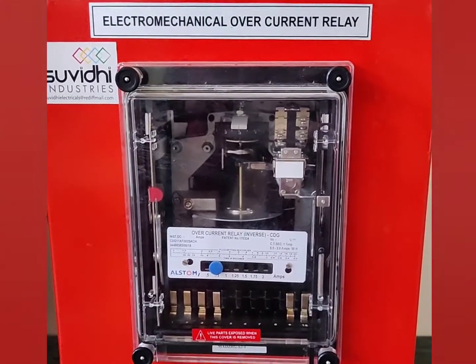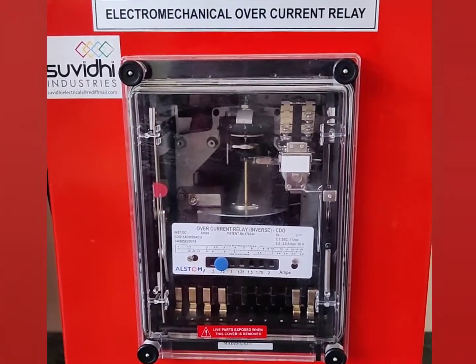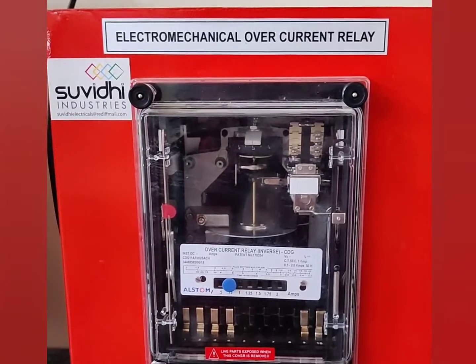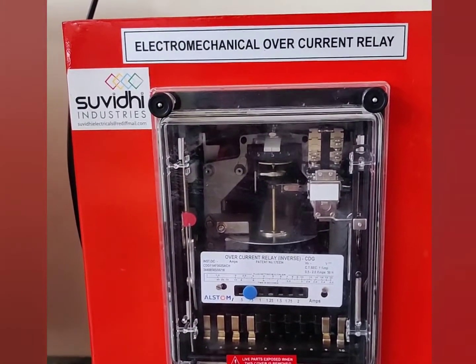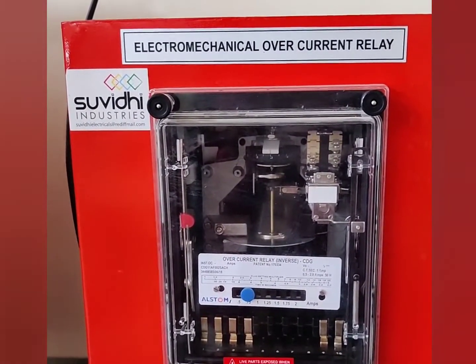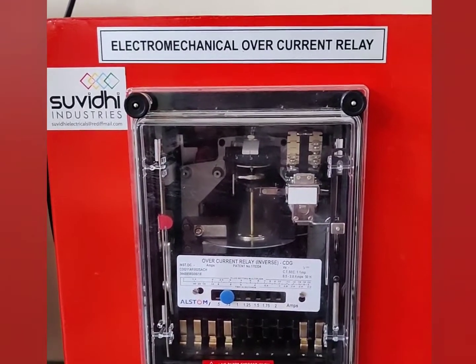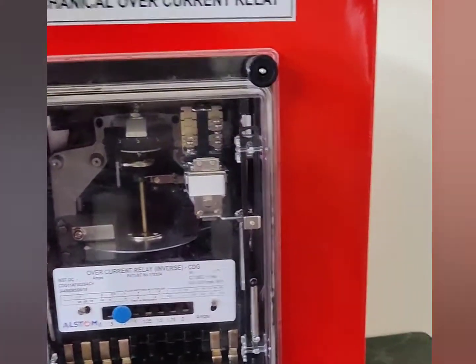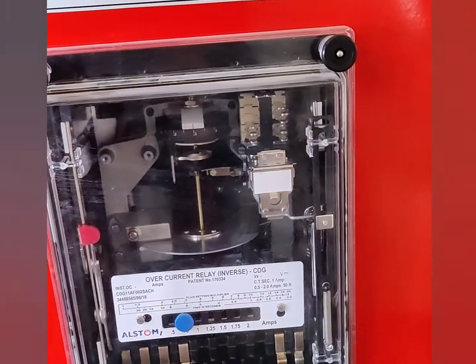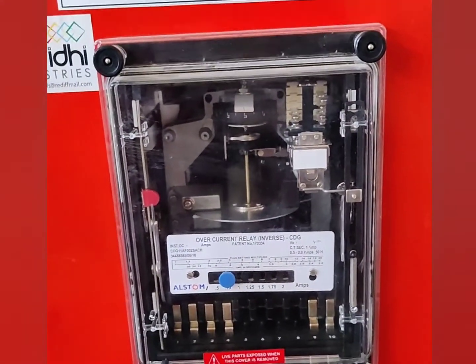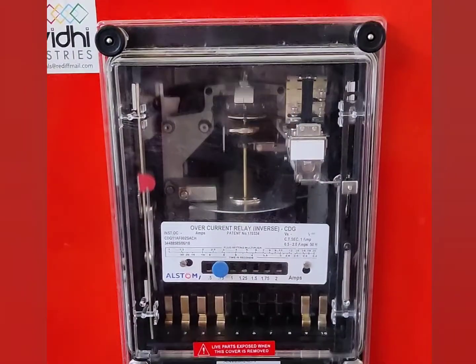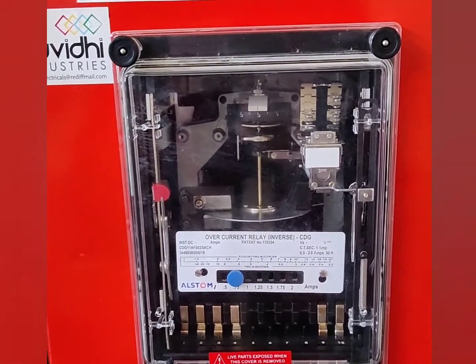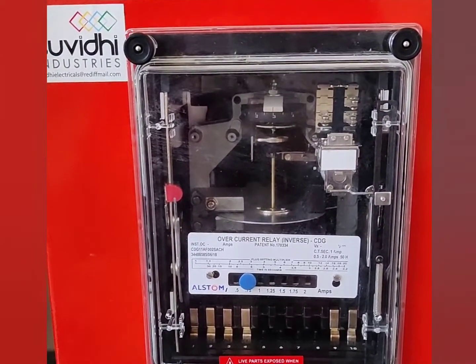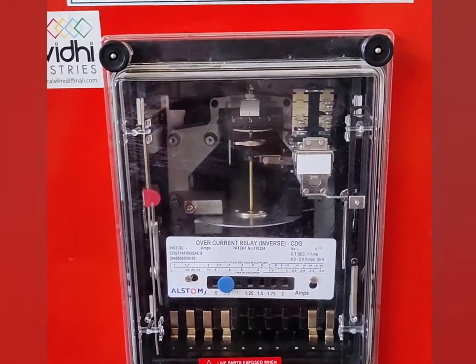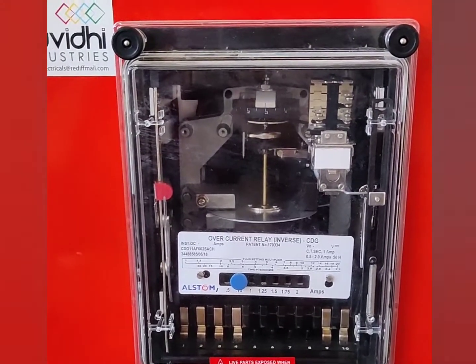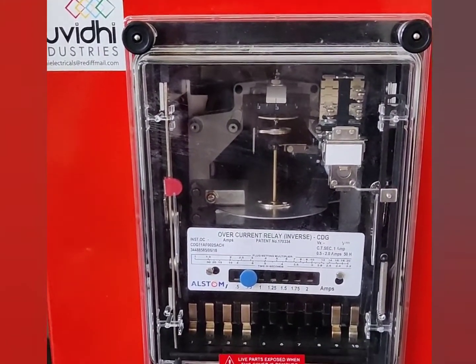So for an example, we have this electromechanical overcurrent relay. Basically, the function of a relay is to sense the occurrence of a fault and give the tripping command to the circuit breaker. So this relay will sense overcurrent type of fault, because you can see that overcurrent is mentioned over here, and once the overcurrent has occurred, this type of relay will give a tripping command to the circuit breaker, and the circuit breaker will trip and isolate the faulty section from the healthy part of the power system.